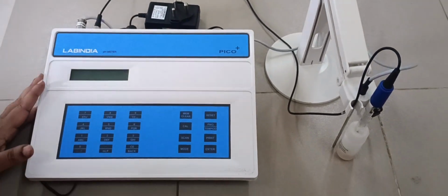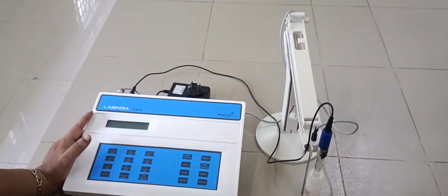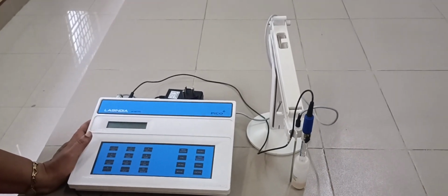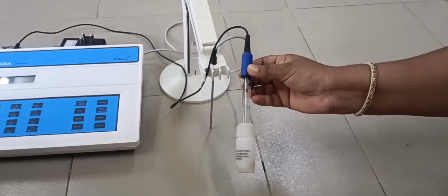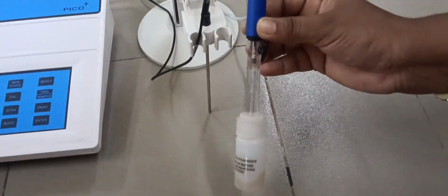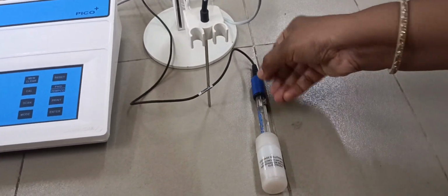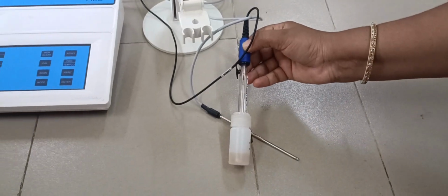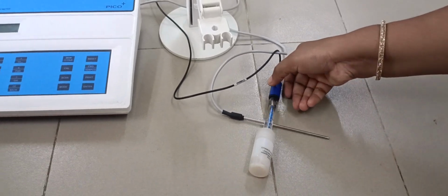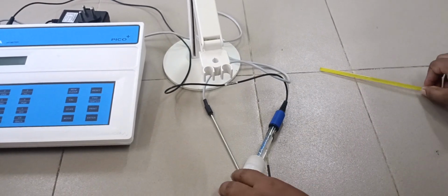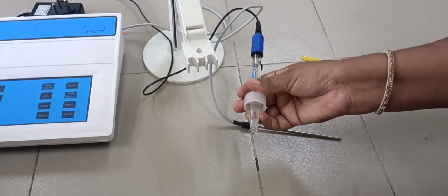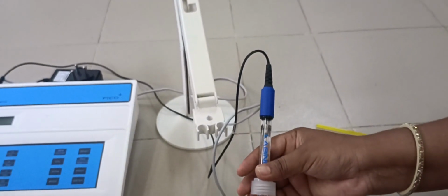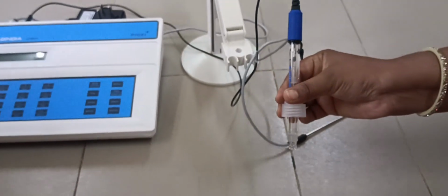Now the electrode. What is the working principle of this pH meter? As we know, the pH meter is used to measure the pH of a solution. The pH electrode contains a pH probe. The probe contains two electrodes: one is the indicator electrode, the other is the reference electrode. The reference electrode is filled with saturated KCl. The indicator electrode is a sensor electrode. It contains a glass bulb, which is a porous membrane. Inside the glass, a silver coated wire is present. In the reference electrode also, a silver chloride coated wire is present.